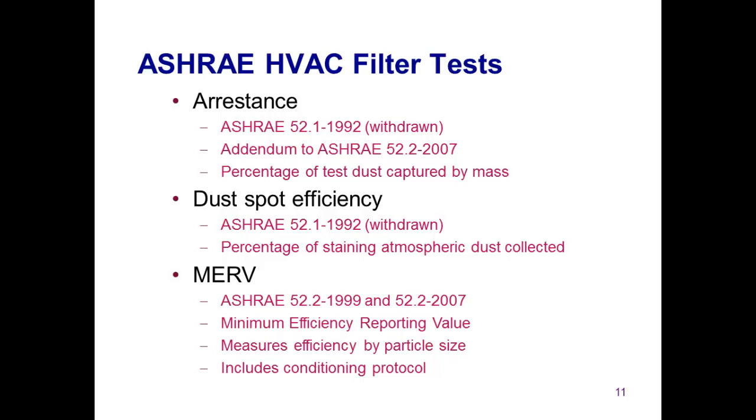The first is arrestance, which was designated in ASHRAE Standard 52.1, 1992. Although this standard has been withdrawn, the arrestance test is included as an addendum in the current ASHRAE Standard 52.2, 2007. This test measures the percentage of a test dust captured by a filter on a mass basis. This is a test that is effective for low efficiency filters.